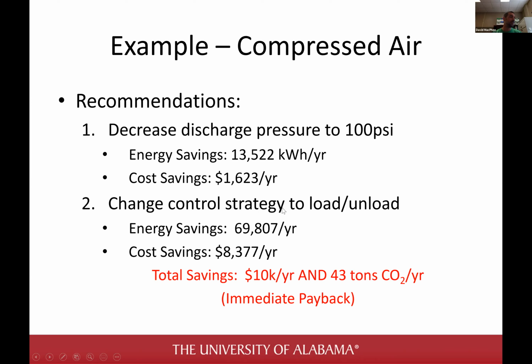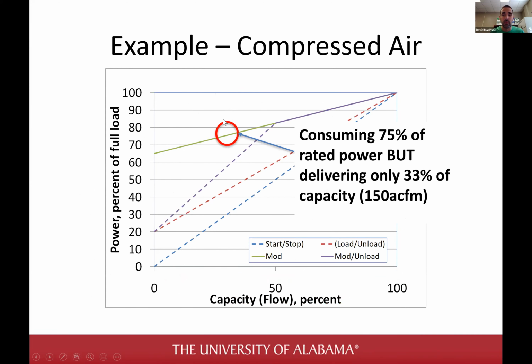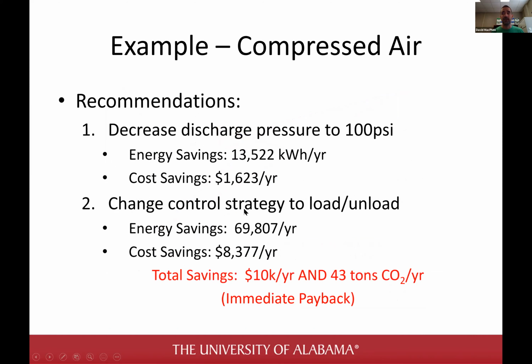And the second thing that we have done before, and this is again an example just to replicate it, you can change your control. If you can change your control strategy to load, unload, you stand to save a lot of energy. Why is that? Okay, why is that? Well, you can go from this red circle here all the way down to the red line. And so you actually save a fair bit on your compressed air costs simply due to the fact that you're load, unload instead of modulating and fighting against that inlet modulation butterfly valve. So yeah, you can do that if you want.